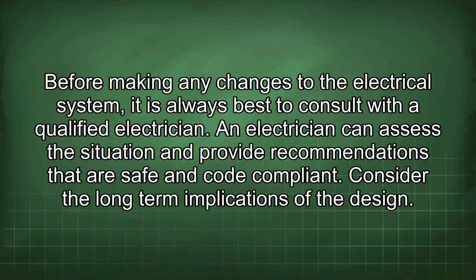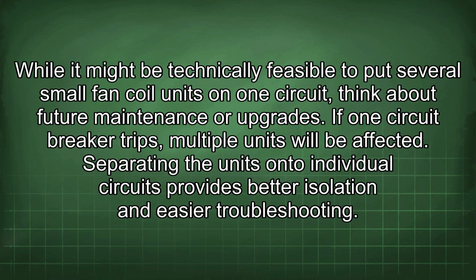An electrician can assess the situation and provide recommendations that are safe and code compliant. Consider the long-term implications of the design. While it might be technically feasible to put several small fan coil units on one circuit, think about future maintenance or upgrades. If one circuit breaker trips, multiple units will be affected. Separating the units onto individual circuits provides better isolation and easier troubleshooting.